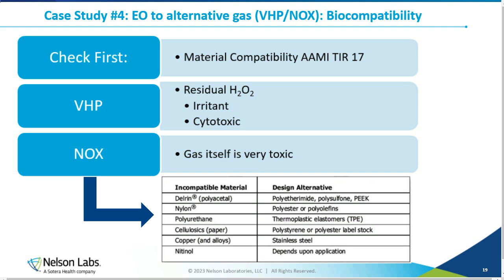So what we would recommend is, if there is a switch to VHP, that some residual hydrogen peroxide testing be performed. Because then, even if it would show up positive in the biocompatibility tests, if we run a residual test and can quantify the amount, we can do a toxicological risk assessment to understand if there would be an adverse effect to the patient based on how the device is used, the exposure, and the patient populations. We could take that into consideration.